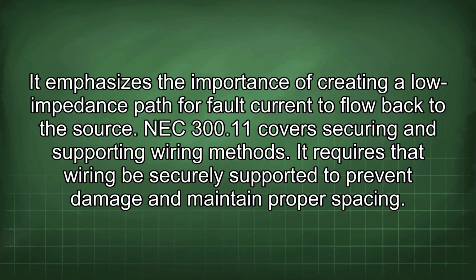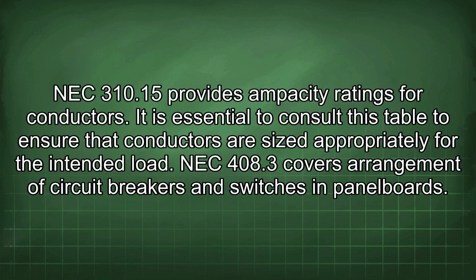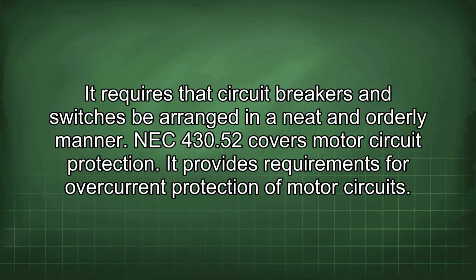NEC 300.11 covers securing and supporting wiring methods. It requires that wiring be securely supported to prevent damage and maintain proper spacing. NEC 310.15 provides ampacity ratings for conductors. It is essential to consult this table to ensure that conductors are sized appropriately for the intended load. NEC 408.3 covers arrangement of circuit breakers and switches in panelboards. It requires that circuit breakers and switches be arranged in a neat and orderly manner. NEC 430.52 covers motor circuit protection. It provides requirements for overcurrent protection of motor circuits.